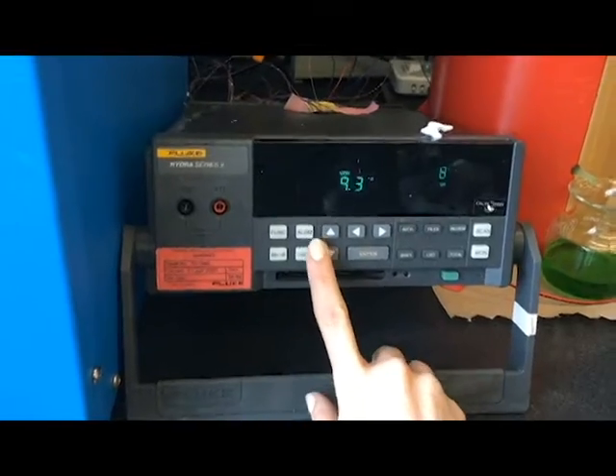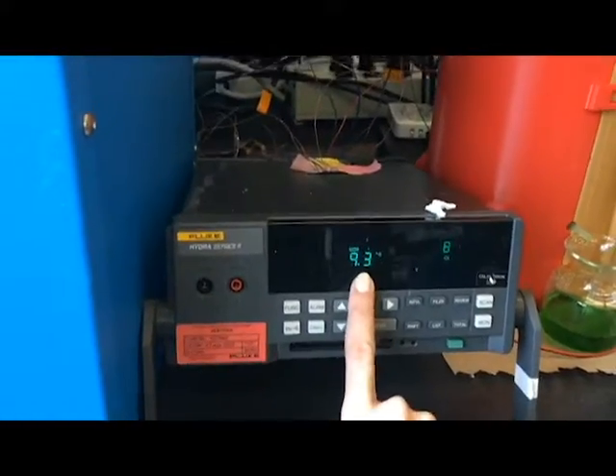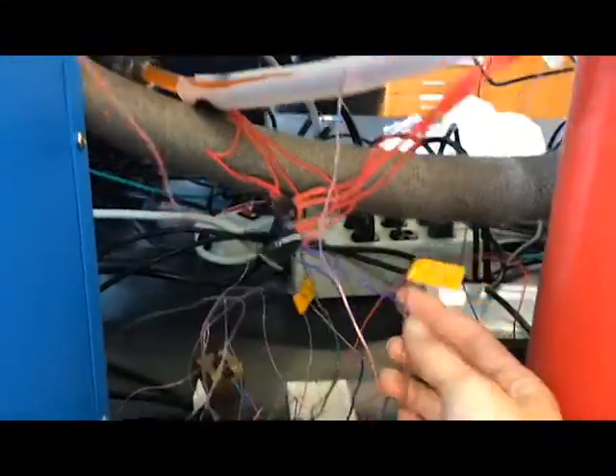As you can see, thermocouple 8 is the one that is located right here between the outlet tube and the heat tape. We have thermocouple number 6, which goes into the top of the housing unit and into the top of the cell chamber. We also have a thermocouple that goes into the chiller, as you can see here. It goes into the chiller bath and is placed next to the outlet tube of the chiller.